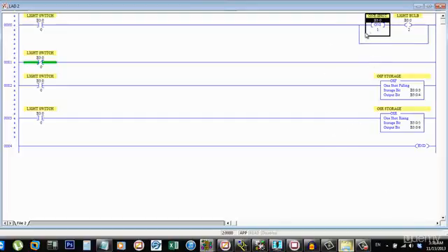Not only is it complicated, but it'll also add some very unpredictable and usually quite undesirable operation to your program. It's going to put a bunch of bugs in there, and people are going to think you don't know how to write a program. So energize a bit one place and one place only. Every one shot gets its own bit.